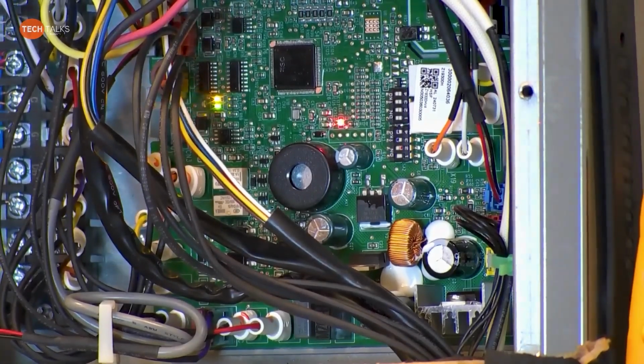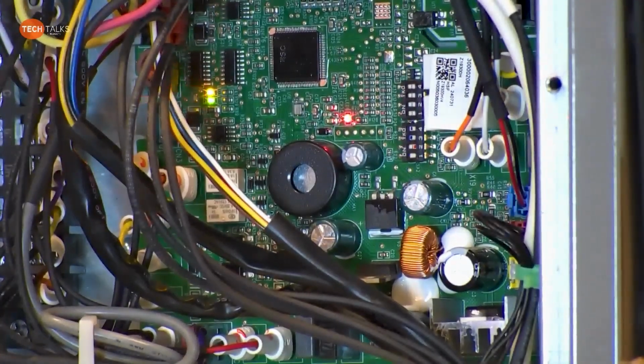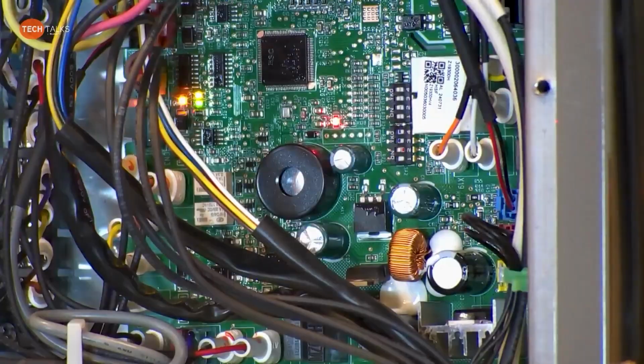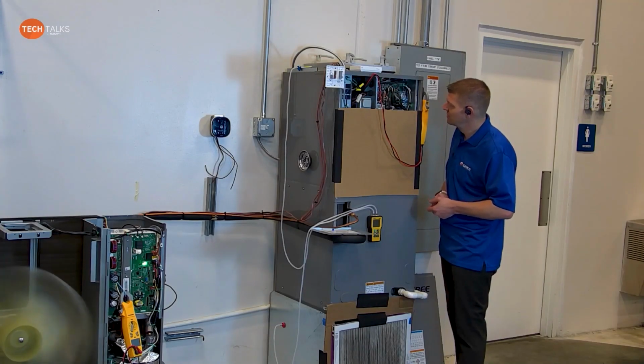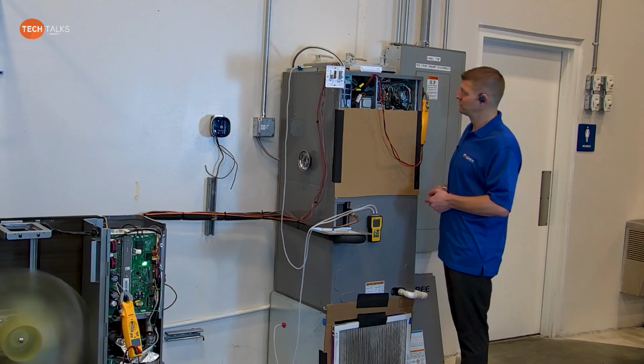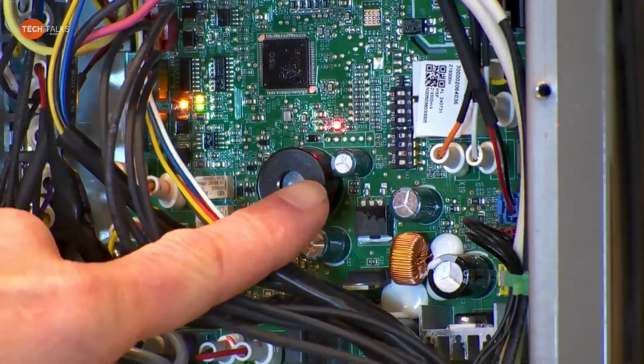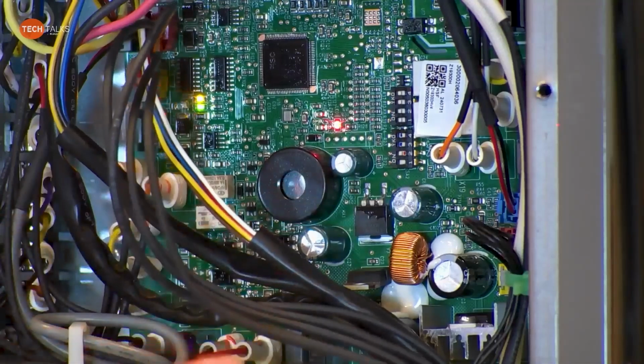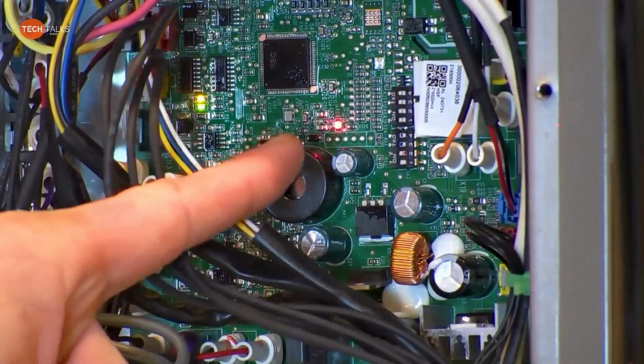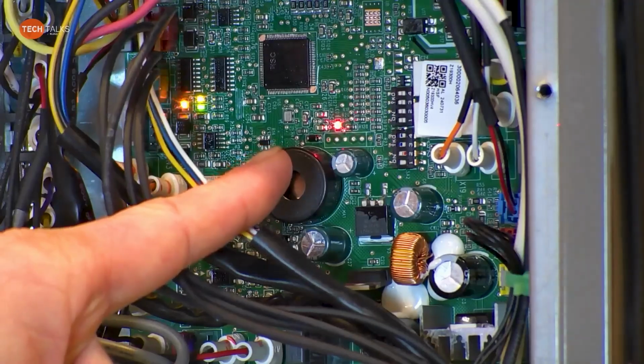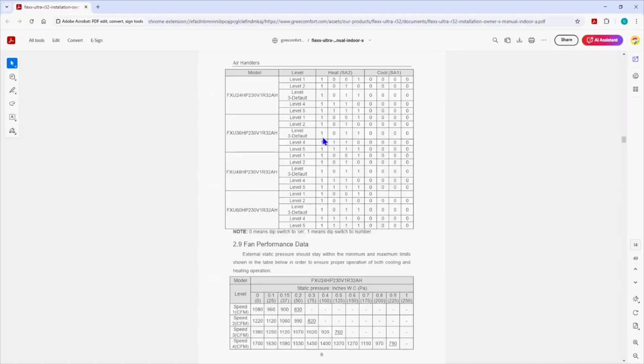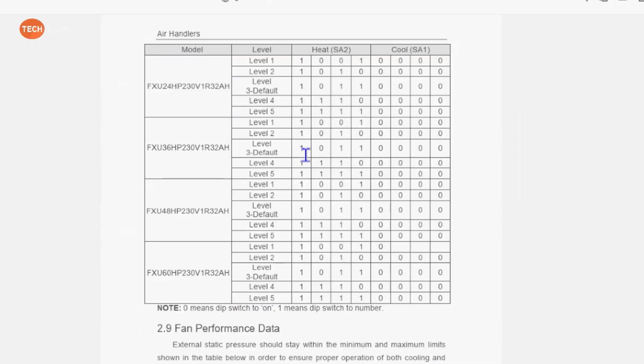So what's our dip switch settings right now for airflow for heating, the SA2 dip switches? 1 is off, 2 is on, 3 and 4 are off on the SA2. The bottom one's SA2, really hard to read, and the top one is SA1. SA1 is all on. Of course, that number 1 dip switch is what we turn on to make it 24 volts. So now I'm going to reiterate what JD was just saying, because I wrote it down. He said the number 1 switch on SA2 is off, which is what 1 means. 1 means off, O means on. And then he said 2 was on.